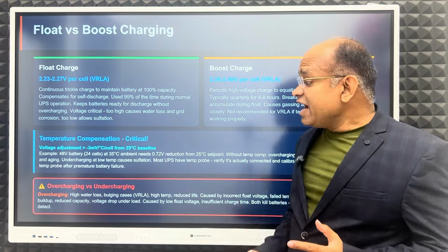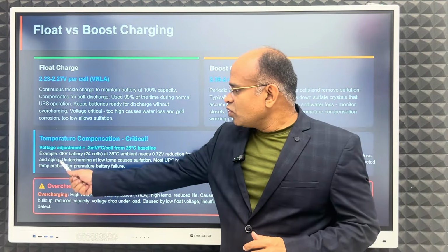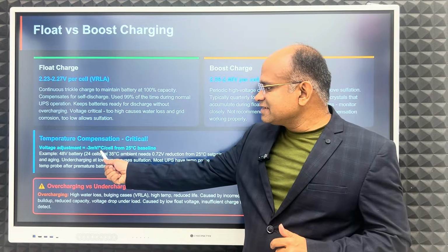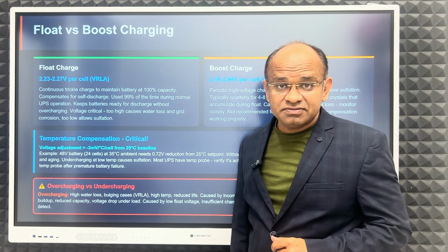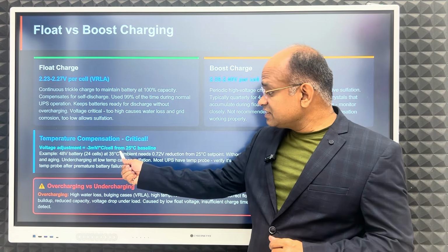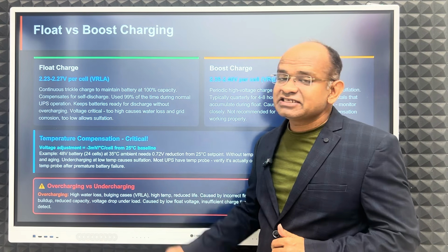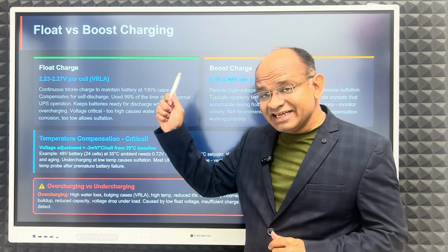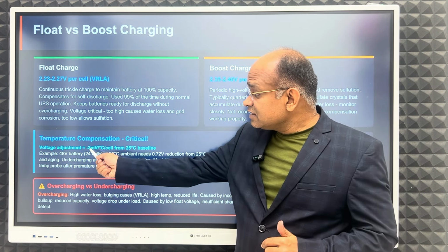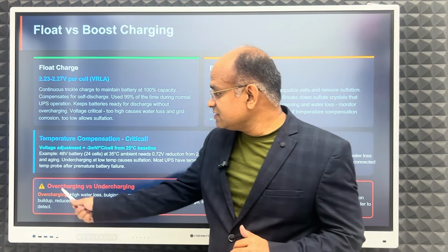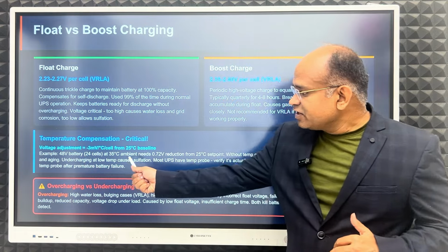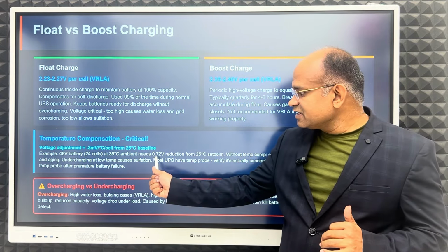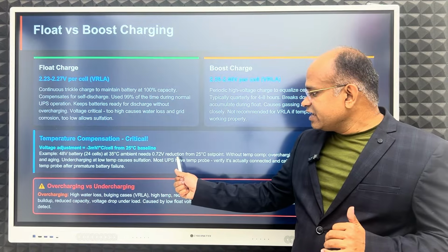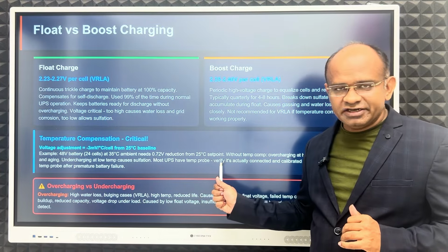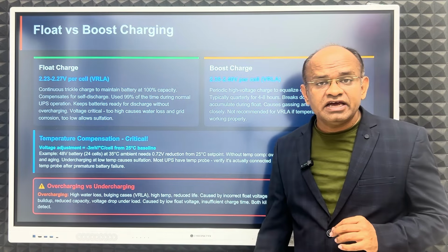Now, why is temperature compensation critical? Voltage adjustment is minus 3 millivolt per degree Celsius per cell from a 25 degrees Celsius baseline. If the temperature increases from there, the voltage adjustment is minus 3 millivolt per cell for every degree Celsius. Example: a 48 volt battery, 24 cells, at 35 degrees Celsius ambient needs a 0.72 volt reduction from the 25 degree set point.